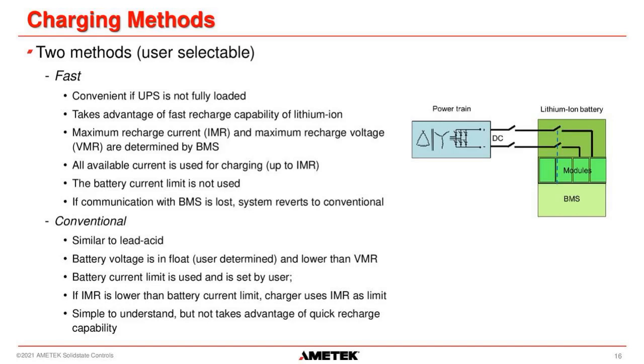When using a lithium-ion battery with our UPS, we have two different charging methods that we can use. First, we have the fast charging method. This charging method will give the maximum current possible to the battery to recharge it quickly, up to 5 times faster than standard lead acid or NiCad batteries. This is convenient if the UPS is not continually operating at full load. If it's at full load, the charger has less current available to use to recharge the battery, because it has to supply the load on the inverter as well.